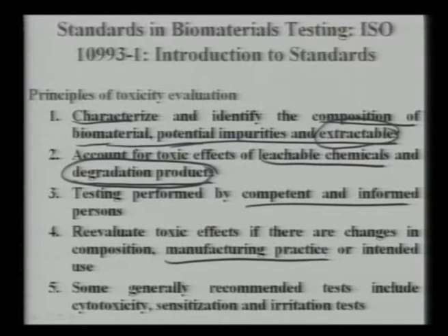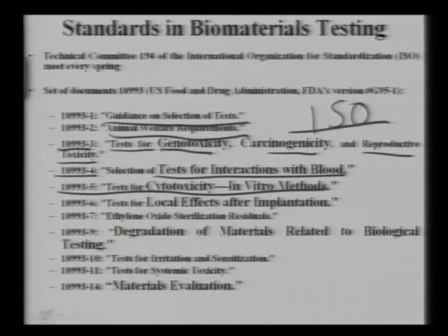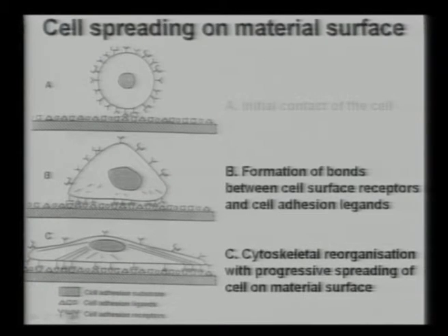Now, some generally recommended tests include cytotoxicity, sensitization, and irritation tests. Now, as I said, the in vitro cytotoxicity, that is the cell culture test, is under the guideline of 10993, and I'll quickly go through what has been summarized in the last lecture.